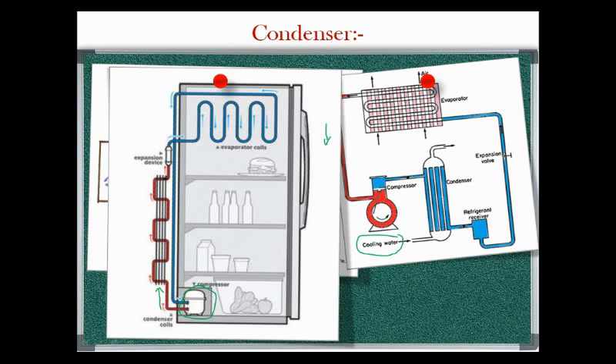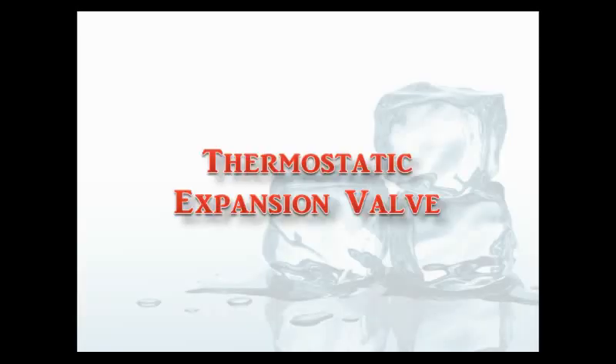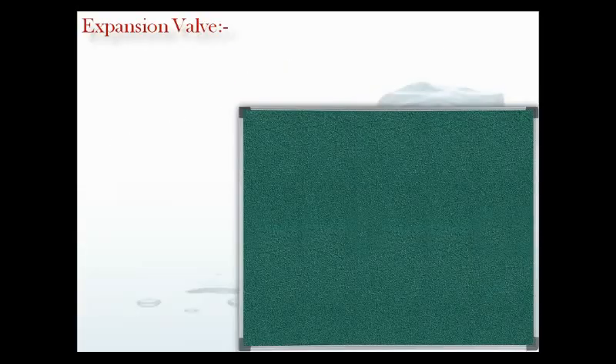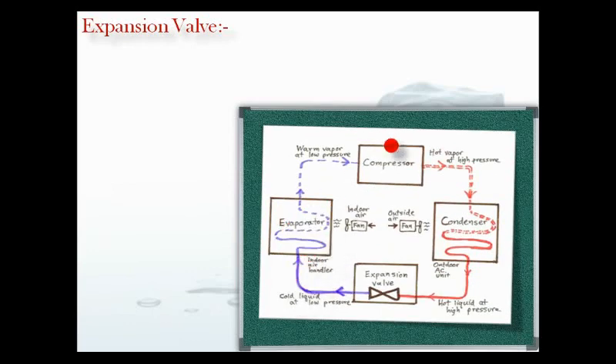At this stage in the refrigeration cycle, the high pressure liquid refrigerant flows down the liquid line through a filter dryer, designed to prevent contamination from flowing through the system, and onto the metering device — which brings us to the thermostatic expansion valve. A thermal expansion valve is a component that controls the amount of refrigerant released into the evaporator, thereby controlling superheating. Thermal expansion valves are generally referred to as metering devices and are flow-restrictive devices that cause a pressure drop of the working fluid.